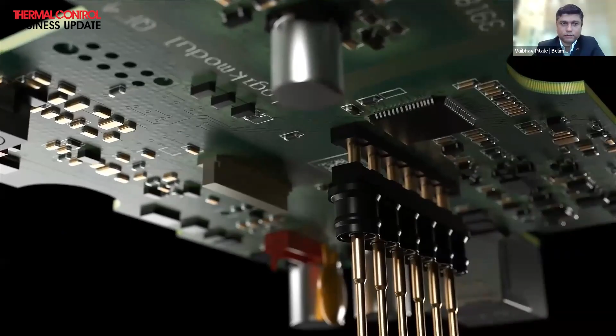So this is one product which is acting as a control valve, which is acting as a balancing valve, which is acting as a thermal energy meter, a BTU meter. It also ensures that at the CRAC unit you're able to manage the delta T. So it's an all-in-one solution, and hence we say the solution is scalable.